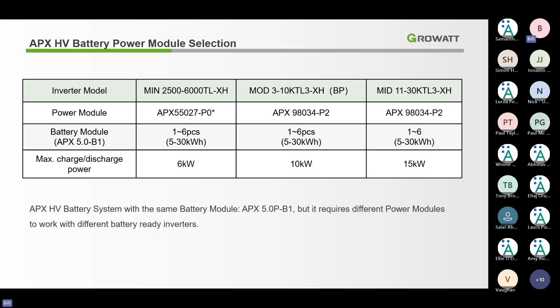The most important thing is the BMS. You can't mix the BMS because we use the same batteries, but the voltage required for single phase and three phase is different. This BMS also comes with a power module and control module. They help the battery achieve the voltage requirement that your inverter needs. So just remember, don't choose the wrong BMS.